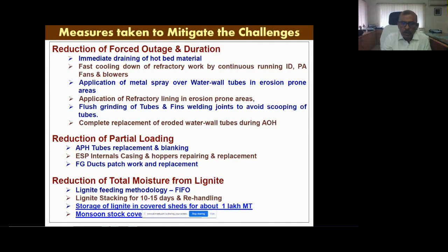Now, fuel is one part; apart from that, I would like to talk about what we have done on the boiler side, which is the major cause of forced outages, almost 95% of forced outages being because of the boiler. If you do normal cooling, it takes 7 days. If you do immediate draining of hot bed material, it takes 1 day, 24 hours. If it is in the other refractory zone area, it takes 2 to 3 days. So we have saved around 4 days. Fast cooling down of refractory by continuous running of ID fan, PA fan and blowers means you are running the auxiliaries and increasing auxiliary consumption, but at the same time we are improving machine availability. So overall, we have seen the options, and it is always better to go for fast cooling. Then only can we achieve availability in the 85% range. Otherwise, it will not be better.